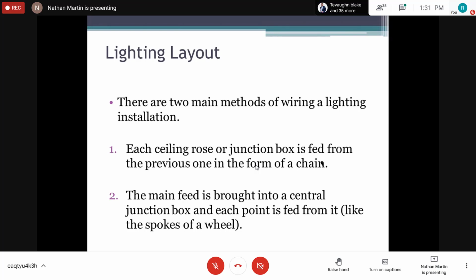Now, one such consumption device is the lighting unit, right? There are two main methods of wiring a lighting installation. One is through a ceiling rose or junction box, which is fed from the previous one in the form of a chain. So this is what we call a looping method. We loop from one box to the next, right? So it's called a looping method, or you can feed from the supply to your individual points. But this is the one that is mainly used, right?